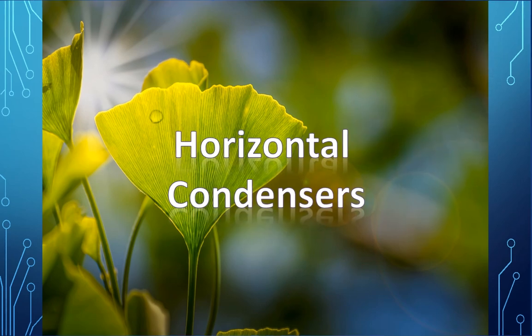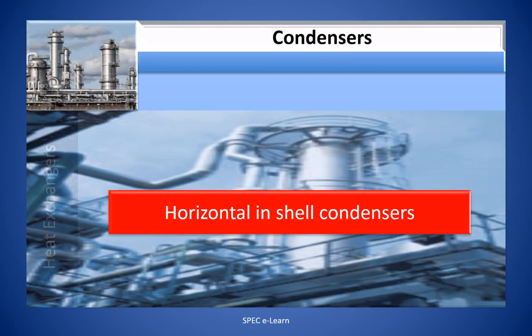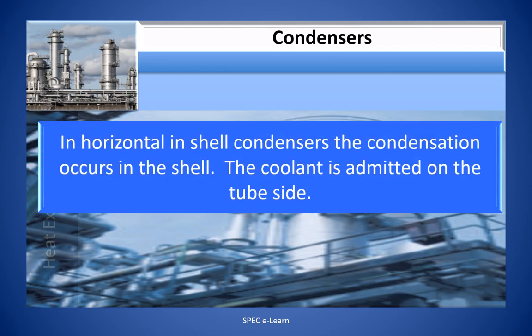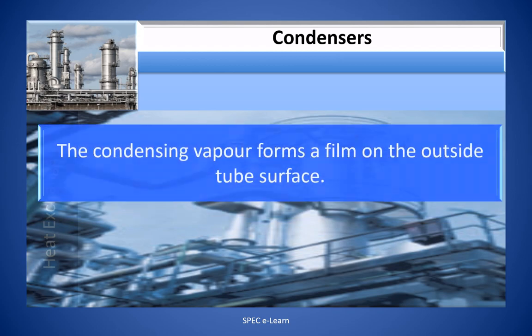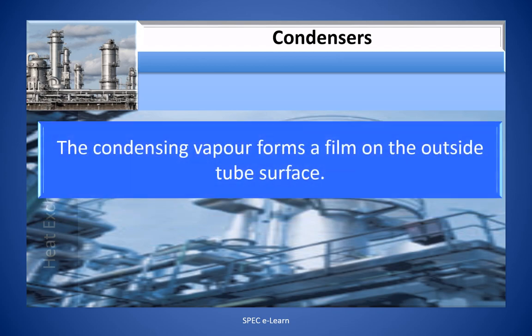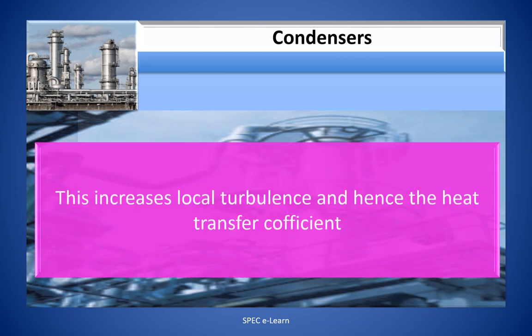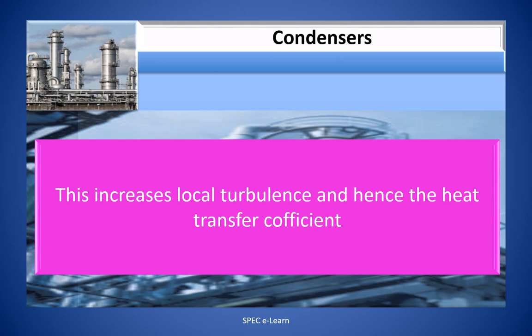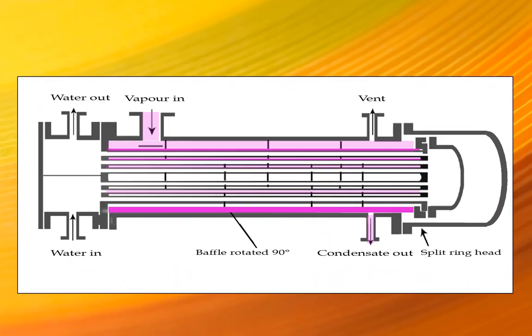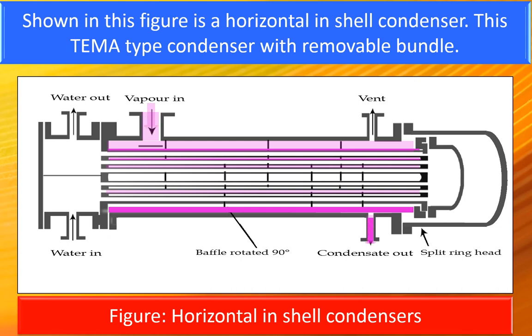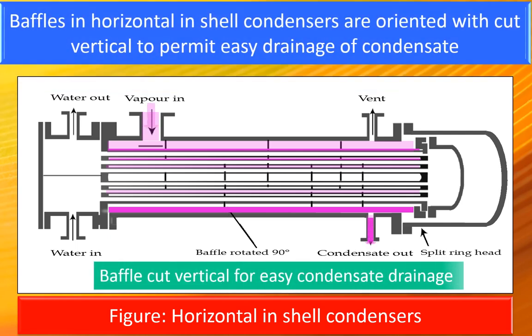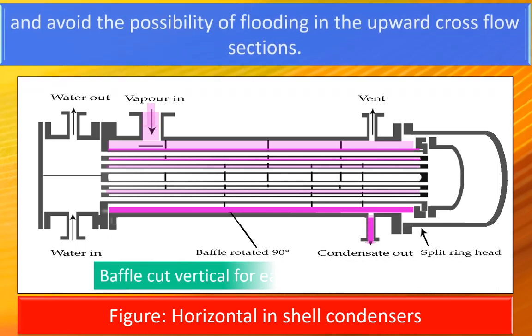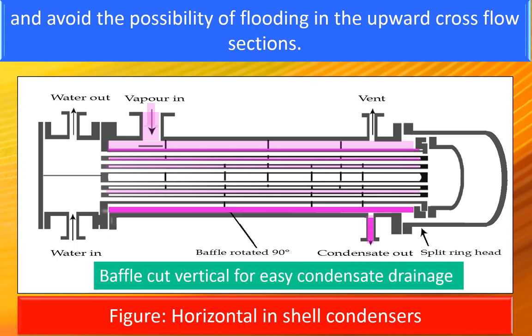In horizontal in-shell condensers, the condensation occurs in the shell and the coolant is admitted on the tube side. This is the most commonly used type of condenser. The condensing vapor forms a film on the outside tube surface; the film falls from tubes at higher levels to lower tubes, increasing local turbulence and hence the heat transfer coefficient. Baffles in horizontal in-shell condensers are oriented with a cut vertical to permit easy drainage of condensate and avoid the possibility of flooding in the upward cross-flow sections.